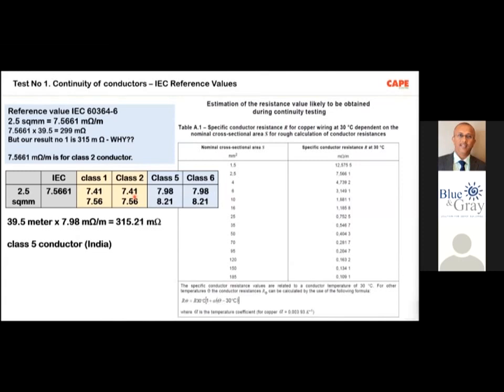Most often, these are not available in the stock, and most often the electricians and people don't know about it. As a result, we always use class 5 copper, plastic PVC wire with class 5 copper. The danger of this wire is resistance is high. As a result, more heat is produced inside the conduit. Technically speaking, the derating factors we are supposed to change. We are supposed to use a higher derating factor.